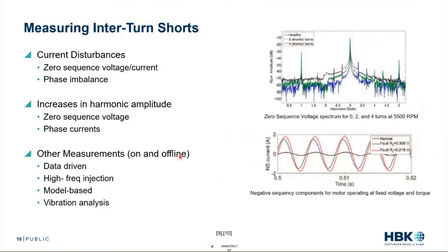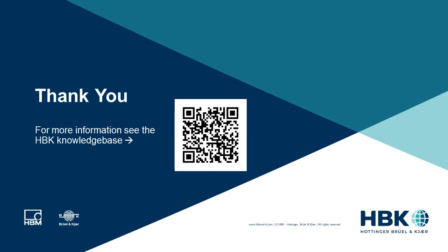There are also other measurements we can use to start to predict turn-to-turn shorts. We can have a data-driven version where we use big data. We can have high-frequency injections — that's more of an online technique. We'd have model-based approaches where we have a model running in parallel, which can be offline or online. And then we have vibration analysis where we can actually look at how that machine is vibrating. So some cool methods — we can start to figure out not only if a fault is happening, but how that's happening. Thank you.